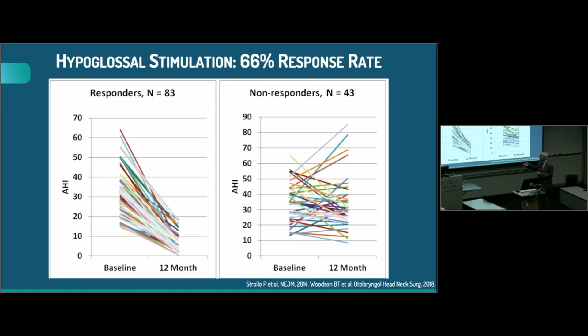Well, the first thought that occurred to us is really how much were we able to improve the airflow? Not just are we able to get a qualitative response, but by how much can we do it? And so we saw a tracing like shown on the next slide, where we had another device, which happens not to have been the original device, that stimulated sort of willy-nilly, sometimes in synchrony with respiration, sometimes out of synchrony. And the stimulus artifact is shown here in the EMG trace, the large ink splatter of black that overlies one inspiration in the middle of this chart. And you can see inspiratory flow once again in the downward direction during the stimulation is roughly double the obstructed or partially obstructed flow that you see in the non-stimulated breaths.